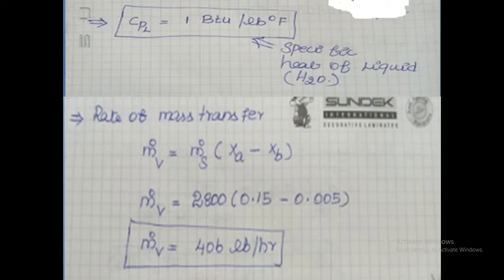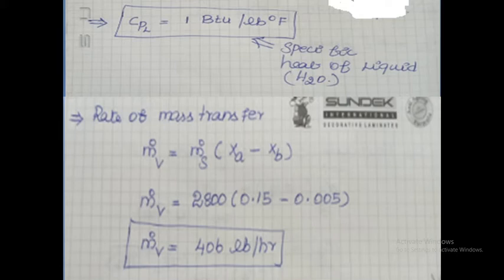The next parameter is rate of mass transfer. Rate of mass transfer M-dot-V is equal to M-dot-S into XA minus XB. M-dot-S is given data: 2800, which is the mass flow rate of solids. XA is given data: initial moisture content 0.15. XB is also given data: final moisture content 0.005. Both moisture contents are on a dry basis. Finally, we get M-dot-V equal to 406 pounds per hour.